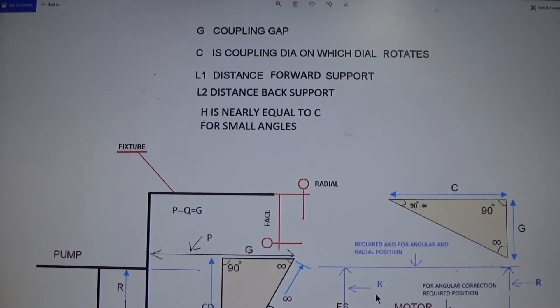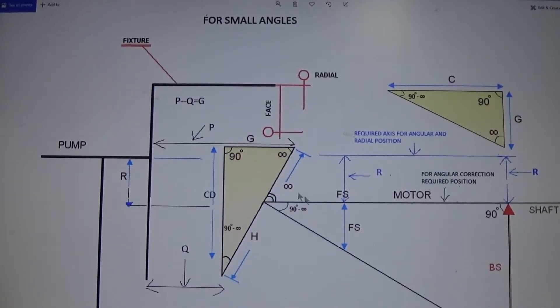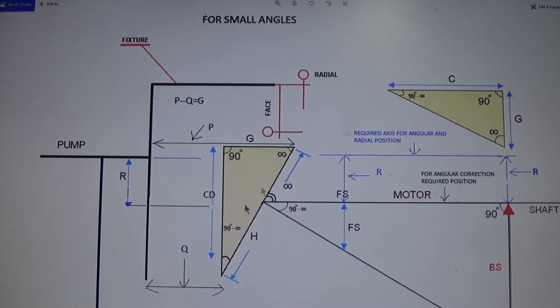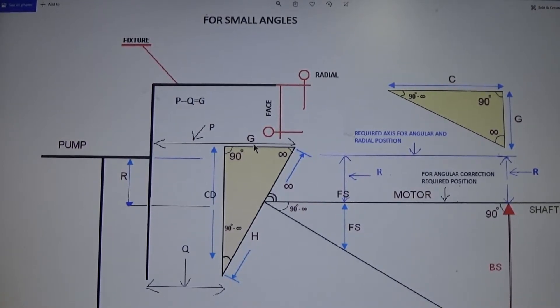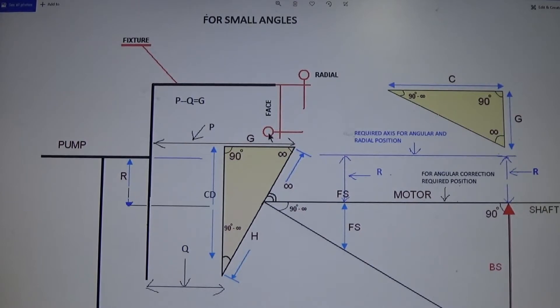In the figure below, G goes from here to here — this is your angular reading, and it is equal to P. P is from here to here, and Q is from here to here. P minus Q is G, the gap difference, which is the same as the angular alignment reading. You may have this with the dial indicator fixed on the face, and this is your rim reading.